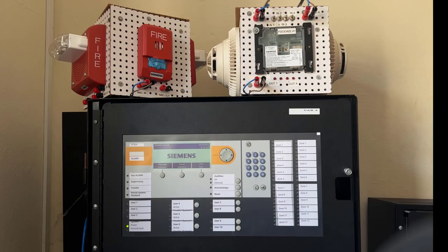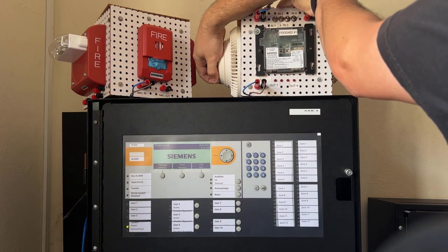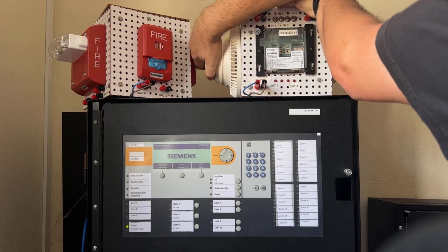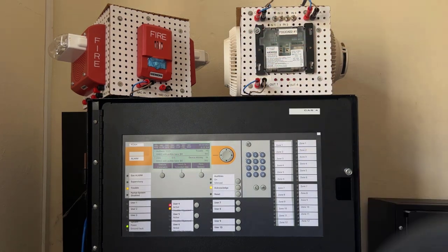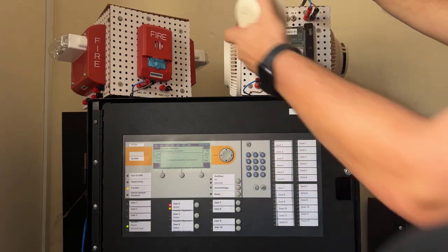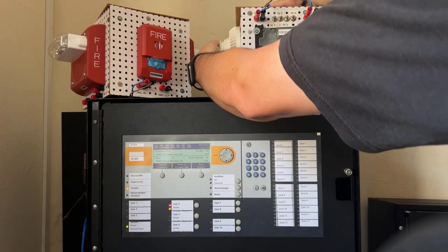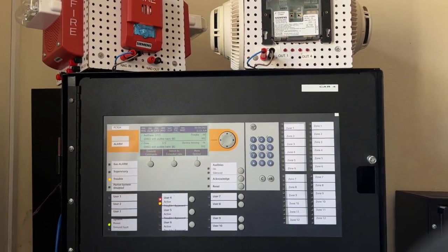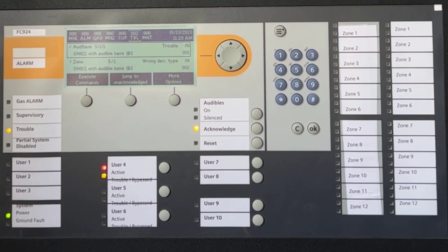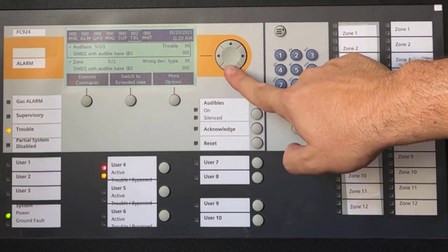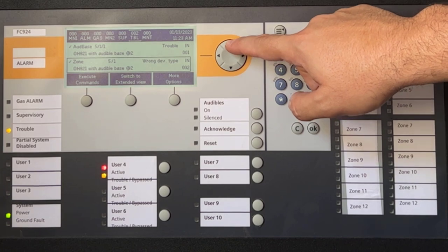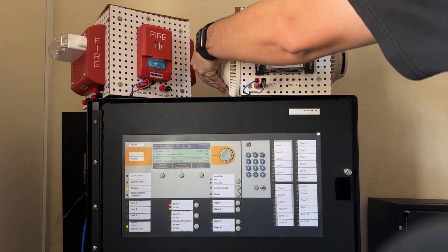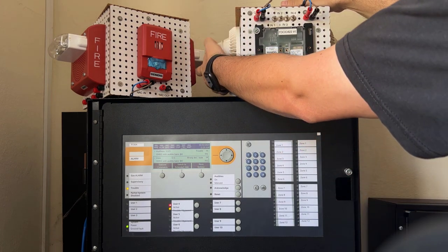And finally, the last scenario in today's video is when the program device type doesn't match what is physically installed on the circuit. I removed an OH921 and inserted an OHC941 with the correct address. As you can see, a wrong device type trouble shows up, along with its associated Audible base trouble. In this case, upon fixing the problem, the system also self-restores back to its normal condition.